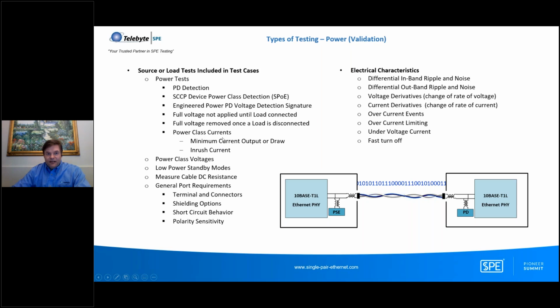And we look at the power class currents. So you saw the low current ranges and the high current ranges, power class voltages. There's low power standby modes. Some of the devices will measure the cable DC resistance. Then we want to make sure that we're using the correct terminal or connector for the application. There's shielding options to tie the shield directly to earth ground or to capacitively couple to earth ground. We want to test short circuit behavior, and then also the polarity of the power. For 10BASE-T1L, it should be insensitive. So whether you have plus minus or minus plus polarity on your DC voltage, we should be able to handle both.